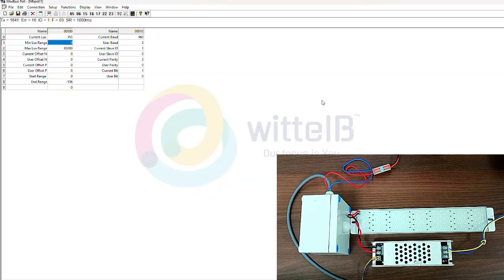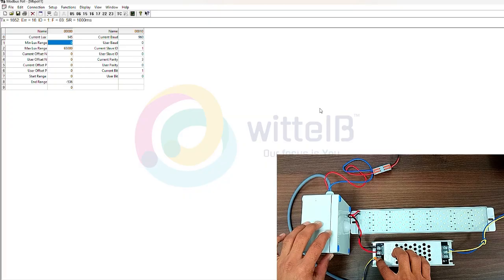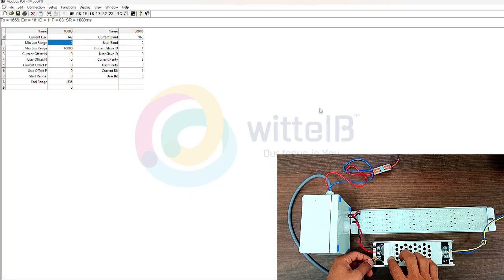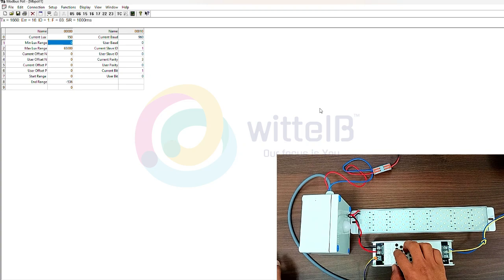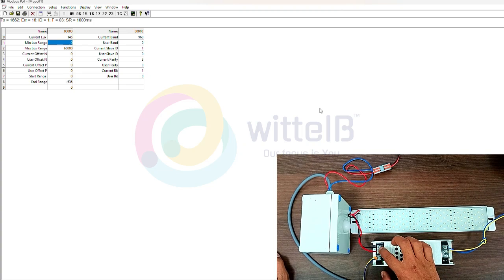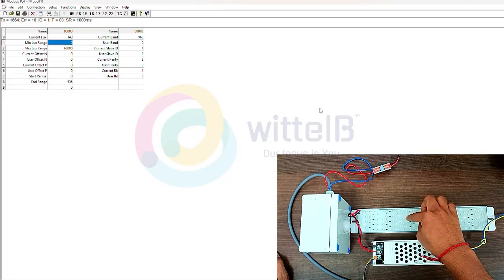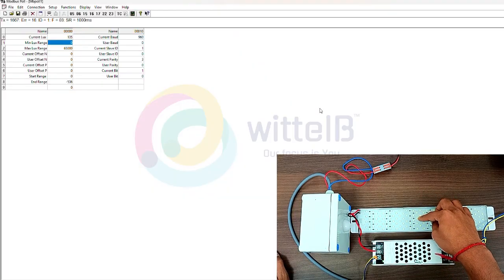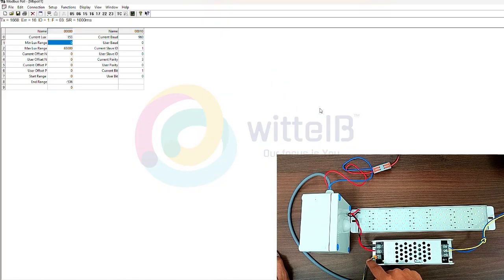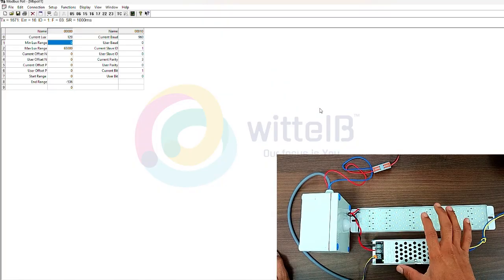Here I have connected the Modbus. For this setup I am using an LED dimming driver. The Lux sensor analog output is connected to the driver input, so it will provide 0 to 10 volt. The driver output will provide 24 volt, and I have connected an LED which runs at 24 volt. This analog output drives the LED based on the Lux.